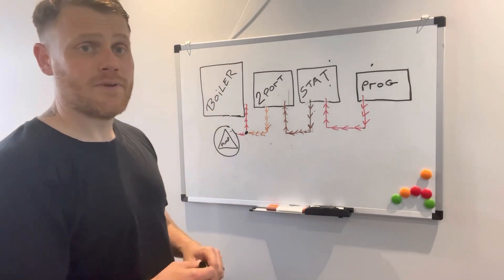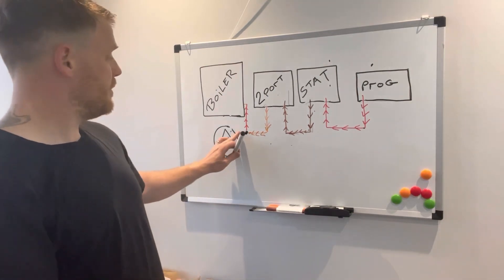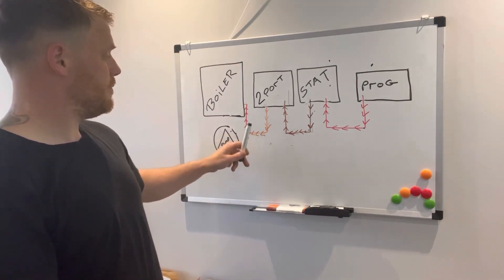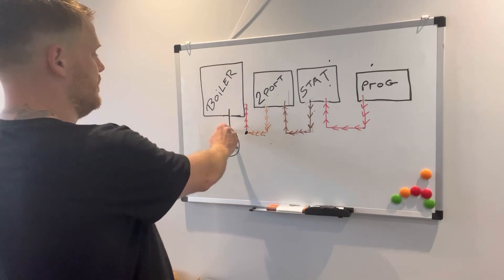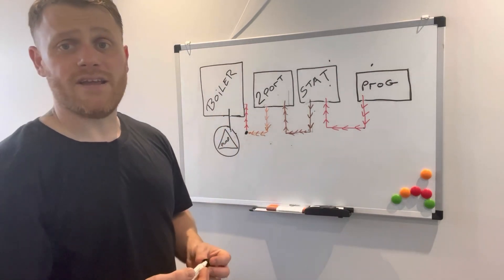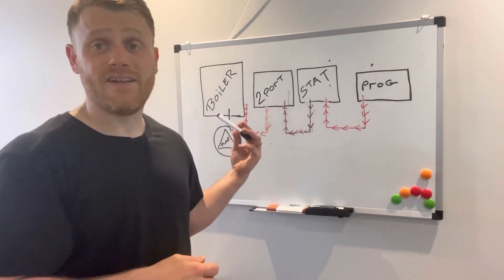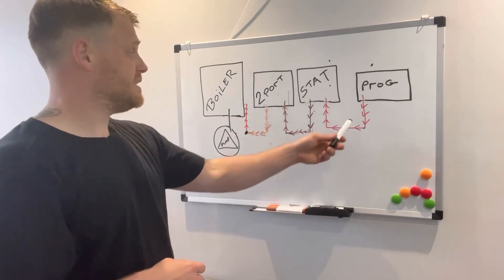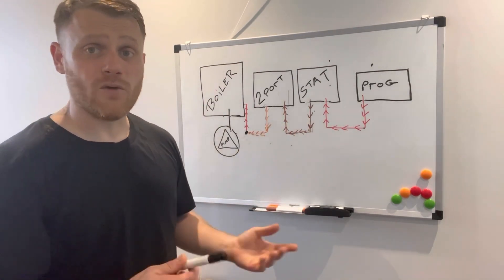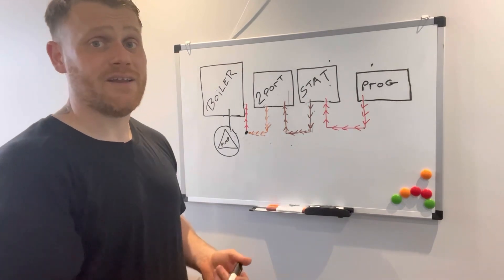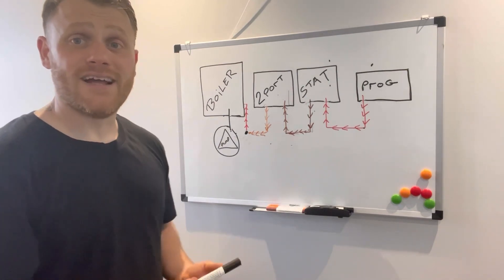Certain setups, Worcester for example, the pump is directly wired into the boiler. That's the only difference I see, so instead of it being there, it should be wired straight into your pump. And that's it, that is how basic S-plan wiring is. It's four or five wires. That's all you've got to remember to wire up an S-plan.